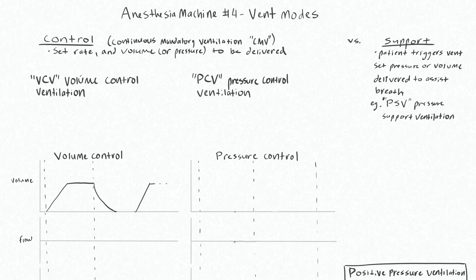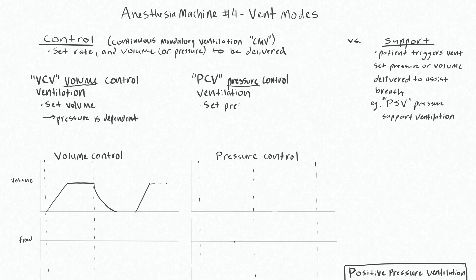You have to choose between either a volume control or a pressure control mode. For the volume control mode, what you're doing is controlling the volume — you set the volume that you want the ventilator to deliver, and then your dependent variable is the pressure. Versus in a pressure control mode, you set the pressure the ventilator is going to deliver, and then your volume is your dependent variable.